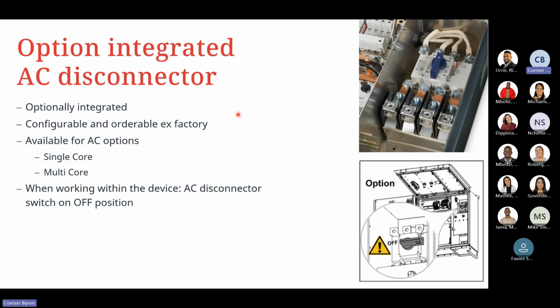From factory, it needs to be ordered with this AC disconnector installed, and it's only available for units that have single core or multi-core cable configuration. So if you're using, let's say, our tower configurator tool and you select the single core and multi-core, you will have the option for the AC disconnector. But if we choose the AC daisy chaining option, the AC disconnector is then not available.